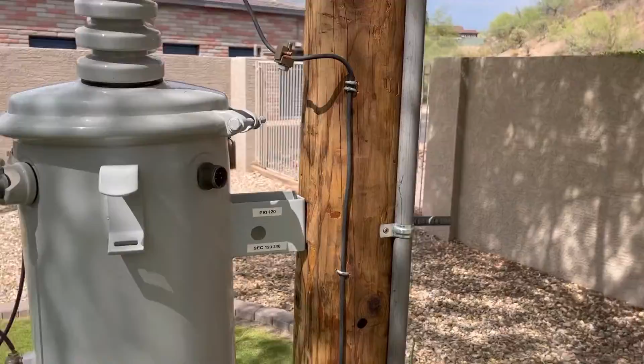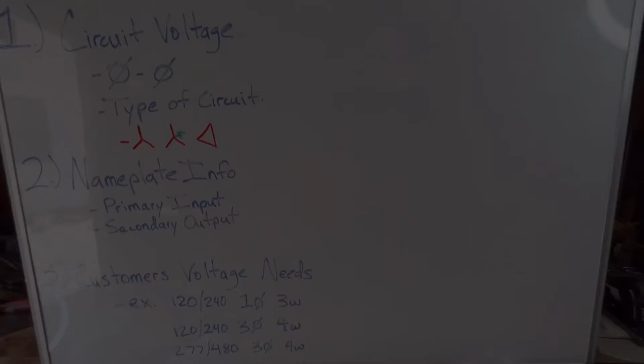So how did I get there? How did I come to the conclusion that I needed to make a phase to neutral connection on my primary side and a single phase delta connection on my secondary side? Well, it comes down to those three pieces of information: circuit voltage, the nameplate information, and the customer's voltage needs. Between those three pieces of information, we can determine both a primary hookup, wye or delta, and a secondary hookup, wye or delta. Let's get into it.